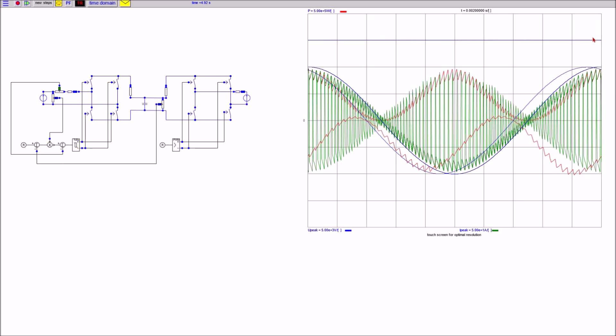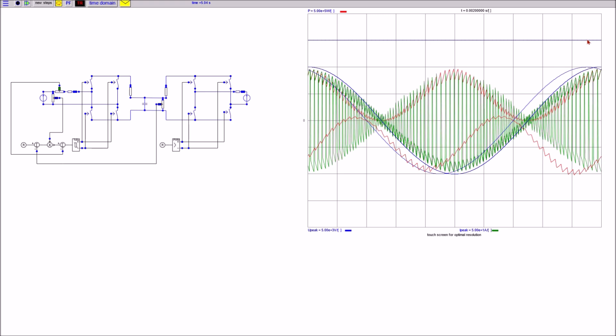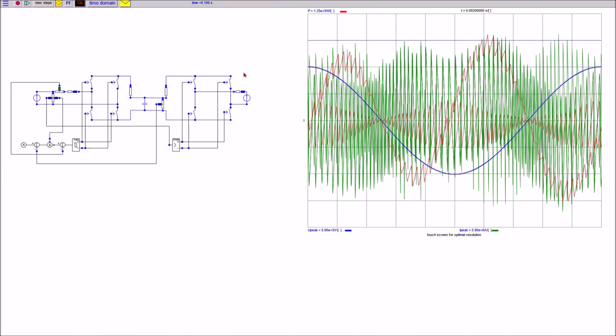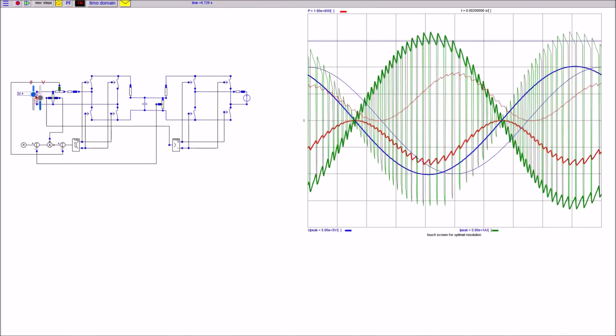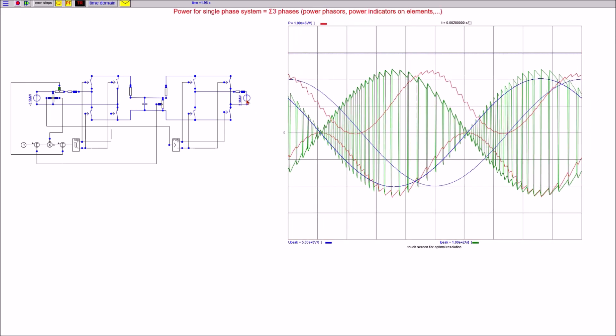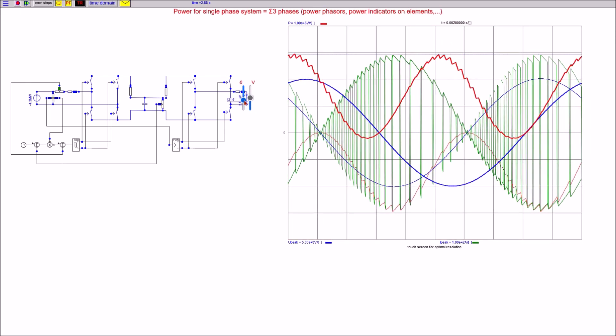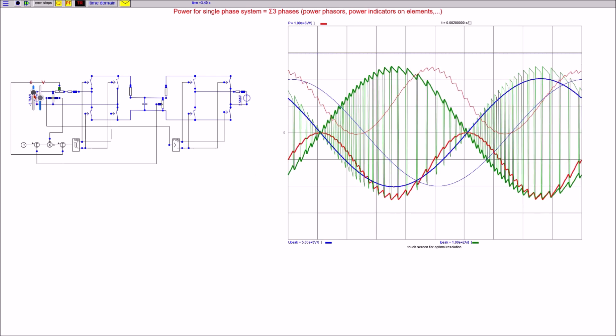Considering the sources on both sides of the DC impacting the power flow on equal terms, I can replace the reference signal by a sensor signal connected to the AC source on the left side. As a result, the power flow now depends on the phase angle difference between both AC sources — exactly the behavior seen earlier between two conventional AC sources connected by an inductor or a line.